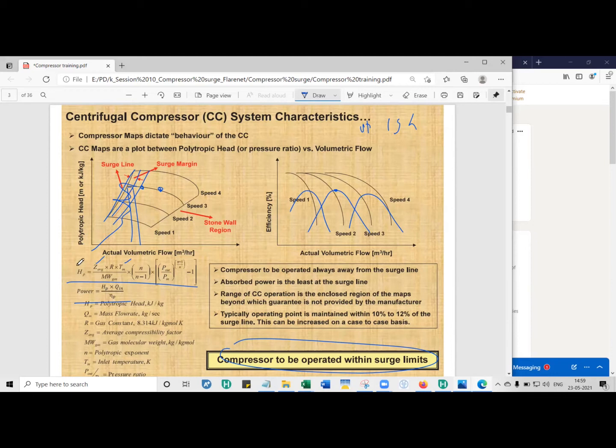With that, we can estimate what is the polytropic head, that is, how many kilojoules of energy is required to compress one kilo of gas from an initial pressure to a final pressure. So higher the polytropic head, higher is the amount of energy required to compress a kilo of gas to the required pressure ratio.